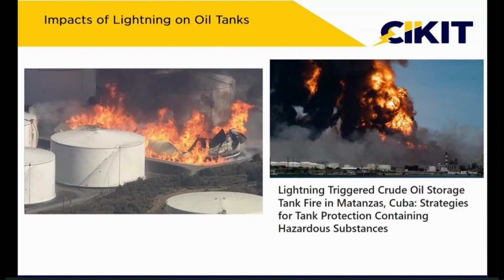So that is the reason we always classify these oil and natural gas storage areas as a high risk zone, and while designing this lightning protection itself, we'll be considering the level 1 protection or level 2 protection. So these regions are highly inflammable materials and the risk of fire and explosion is very much higher on these particular oil storage areas. So they need additional protection than this normal protection which we are giving.